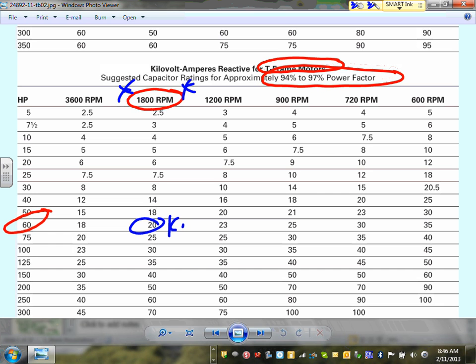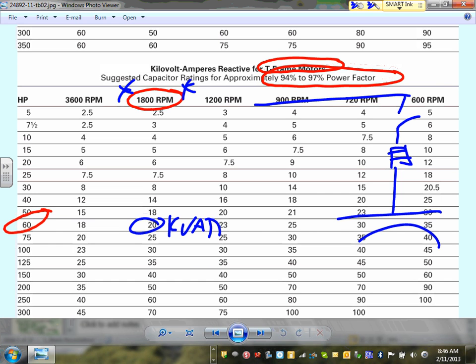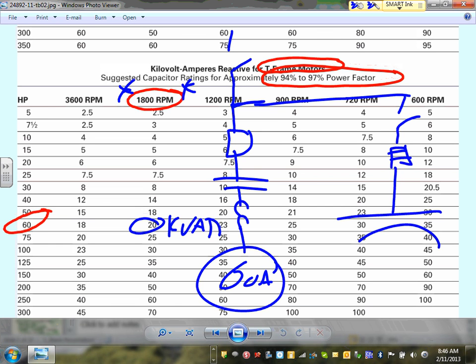So that will get you kVAR. That'll give me a 20 kVAR for this system. So now I know what the capacitor size is. So I put my capacitor and go put my fuse and my disconnect and bring it all the way to here's my motor, tie it right here. Here's my disconnect for my motor, here's my overcurrent device, my controller, my overload, and here's my motor, the 60 horsepower motor. And what size will this baby be? 20 kVAR. Does that make sense? Here's my 60 horsepower. That's how we size it for motors. We will be using this table tomorrow, my friend.